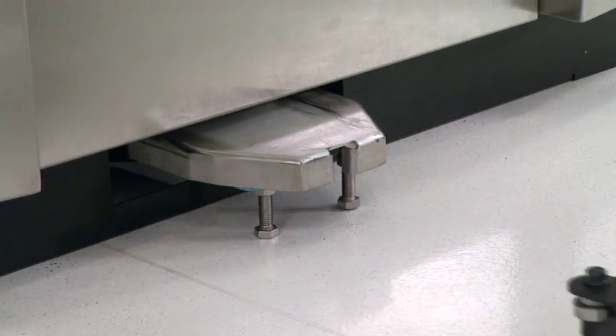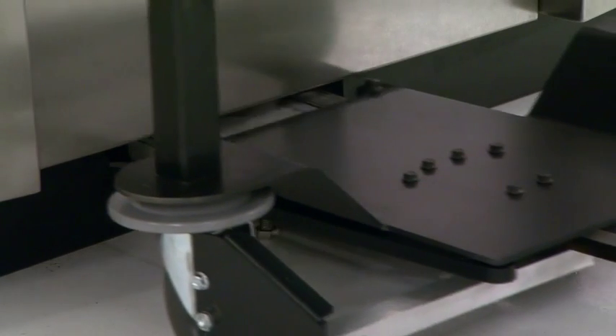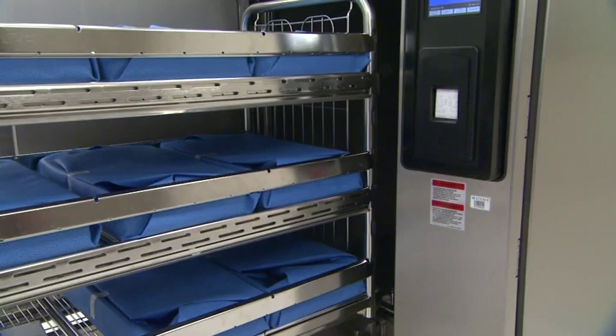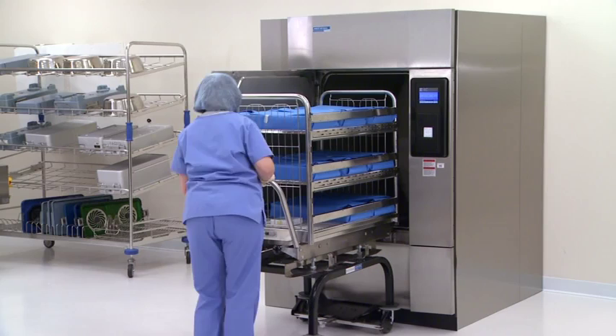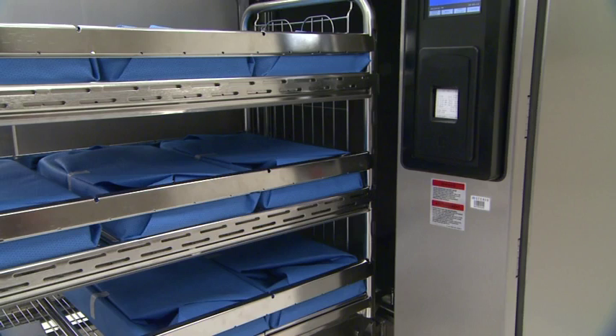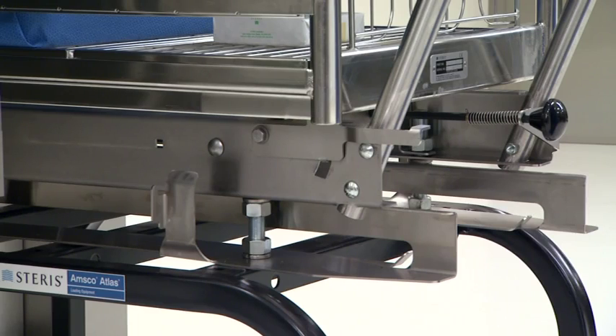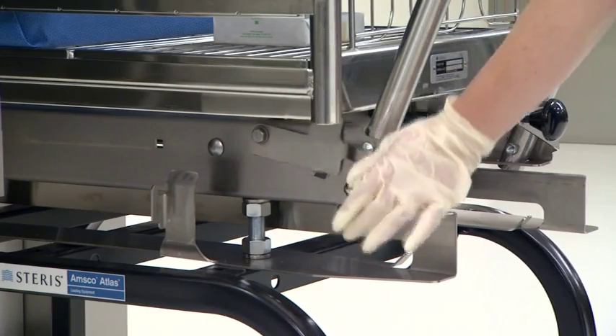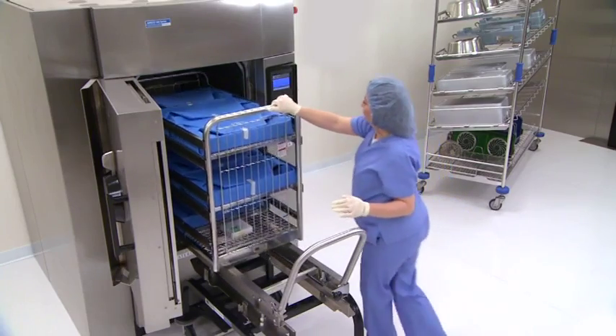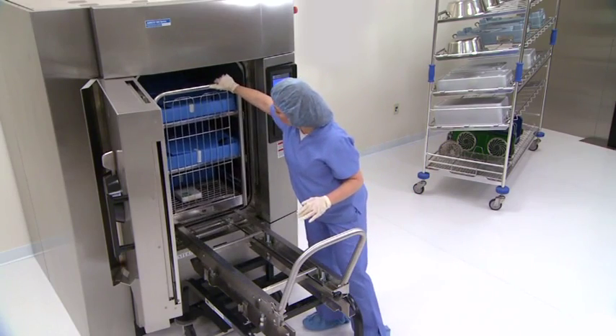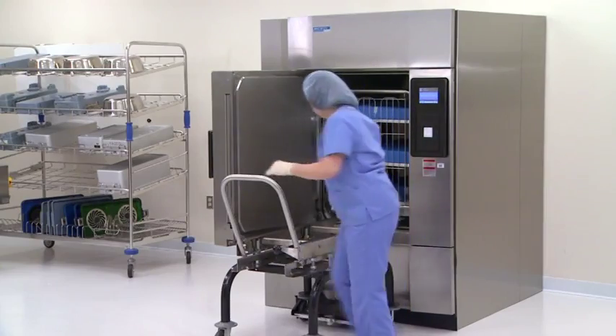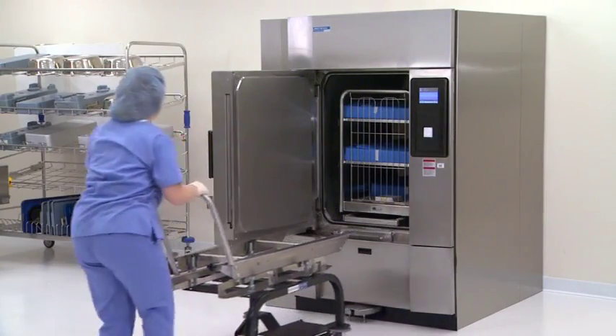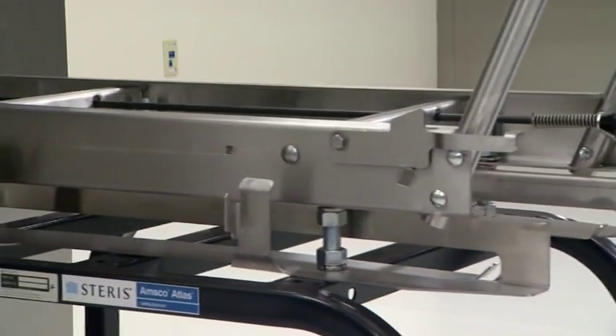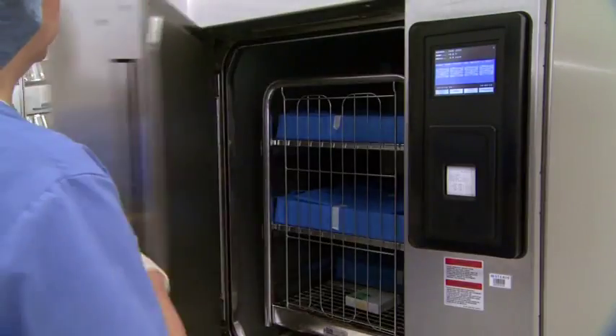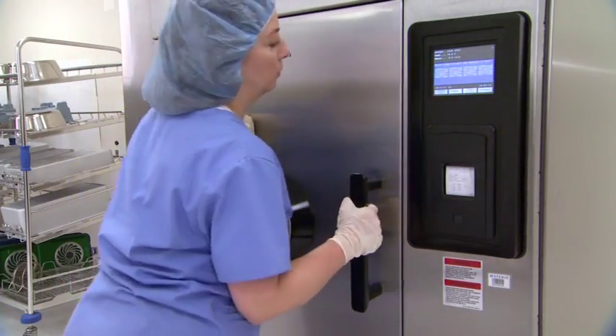Once the transfer car is aligned, press the carriage forward until the latches mate with the holes in the chamber end frame bracket. Verify the transfer carriage is securely latched by pulling the transfer carriage backward. The transfer carriage should remain stationary. Once the transfer carriage is securely latched, release the loading car from the transfer carriage by pushing down on the carriage lock. Carefully push the loading car off the transfer carriage and fully onto tracks in the sterilizer chamber. Disengage the transfer carriage latches from the end frame by pulling the carriage latch knob. Back the transfer carriage away from the sterilizer and close the chamber door. The sterilizer is now ready to run a cycle.